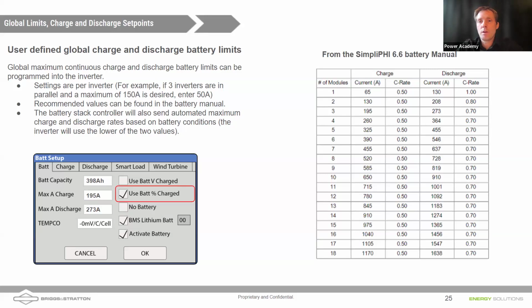For two batteries, 208 amps. For three batteries, it would be 273 amps. But note that the Sol-Ark is going to limit your output current at 275, so you won't be able to go above that for a single Sol-Ark. It's also important to keep in mind that these batteries operate at about 50 volts, and at 50 volts, your real amperage limit is going to come from the power. 12 kilowatts of power is only going to pull 250 amps max. So a single stack of 3 batteries can power a Sol-Ark 15K completely, meaning full power output. The maximum charge rate at C/2 for 398 amp hours, you essentially divide that in 2 and you'd get 195. I believe it's closer to 198 amps, something like that.